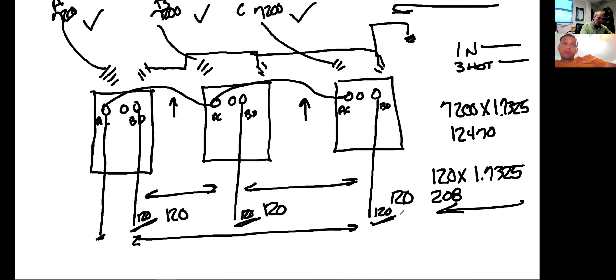Professor V, anything you'd like to add there? Just remember, guys, the tie-in bus on a Y bank is not energized, that's for the neutral, which is reverse on the delta bank, where they're actually connected through the hot terminals on the transformers.